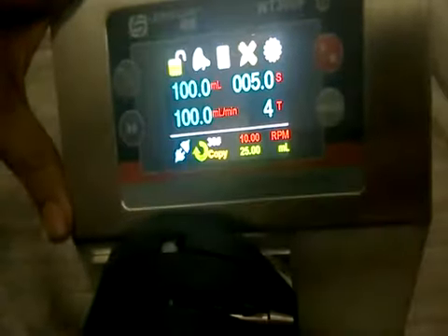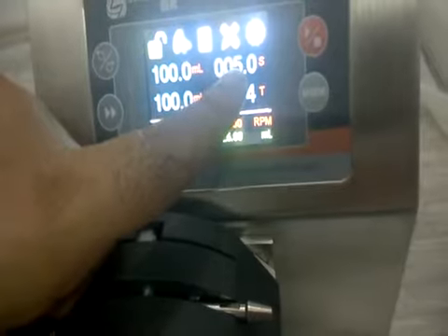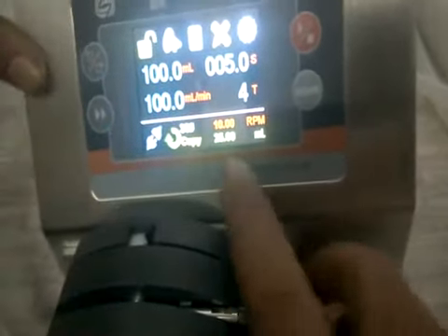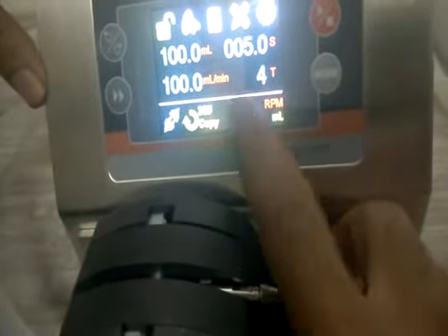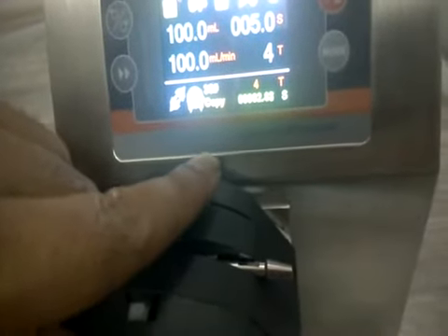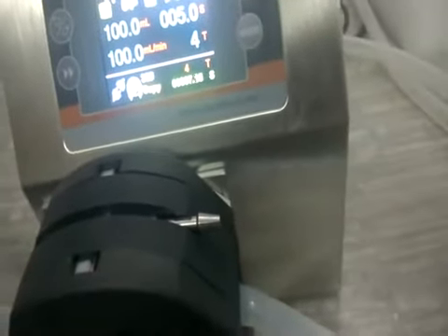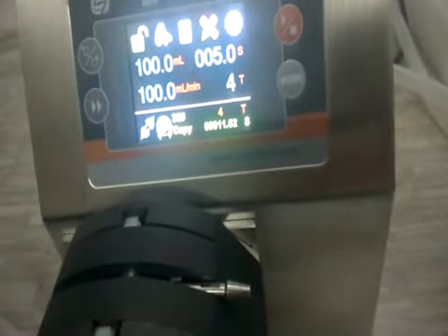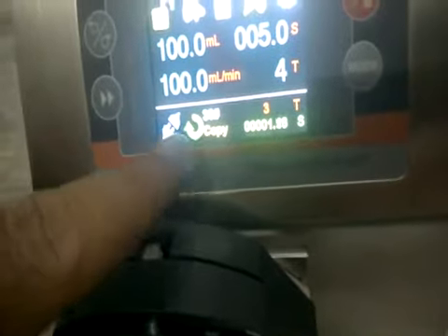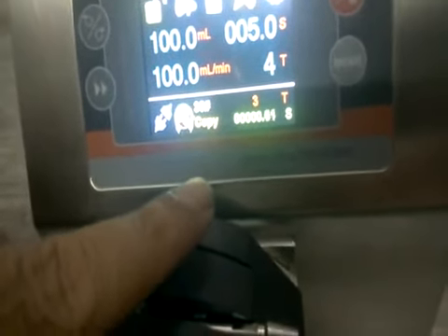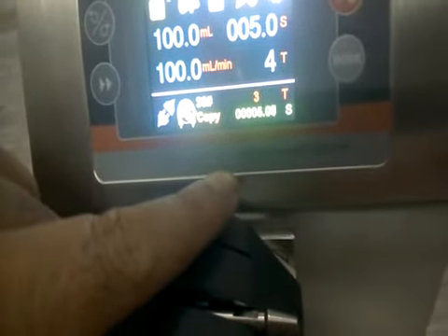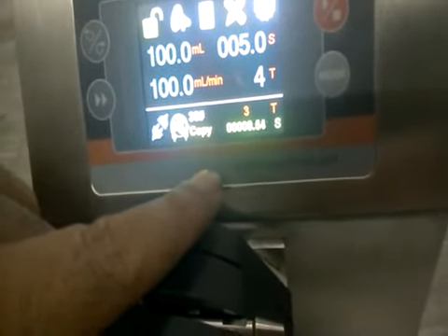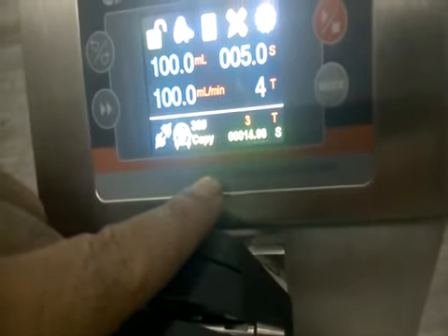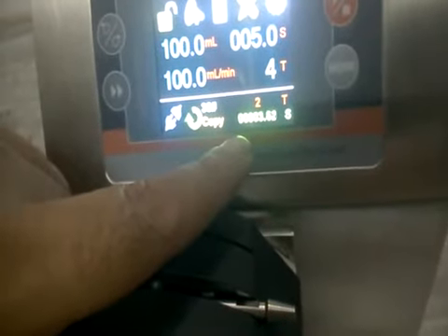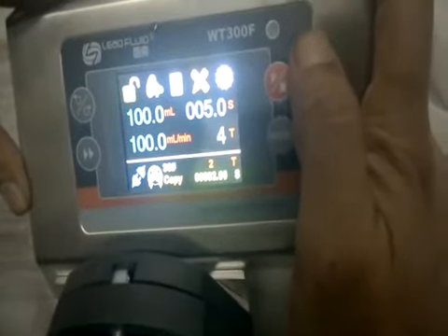If you want to dispense say 100 ml in 4 cycles with a gap of 5 seconds, now it will do that. Let's see. In each cycle it will dispense 25 ml. 25 ml it will dispense, then it will stop for 5 seconds, 25 ml, 5 seconds, wait, like that. So it will dispense 25 ml. Again second dispense, it will again dispense 25 ml. In 15 seconds it is dispensed, now again waiting for 5 seconds. So these are very, very good functions, and that is why this pump is called a smart pump.